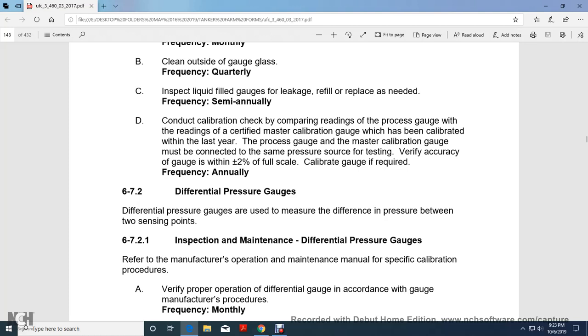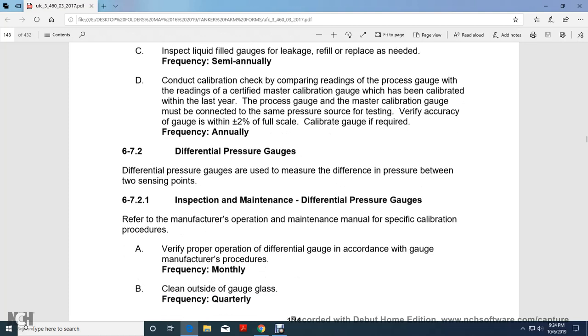Conduct calibration by comparing readings of the process gauge with the readings of a certified master calibration gauge that has been calibrated within the last year. The process gauge and the master calibration gauge must be connected to the same pressure source for testing. Verify the accuracy of the gauge is within plus or minus 2% of full scale, and calibrate the gauge if required. Differential pressure gauges. Differential pressure gauges are used to measure the difference between the pressure at two sensing points.